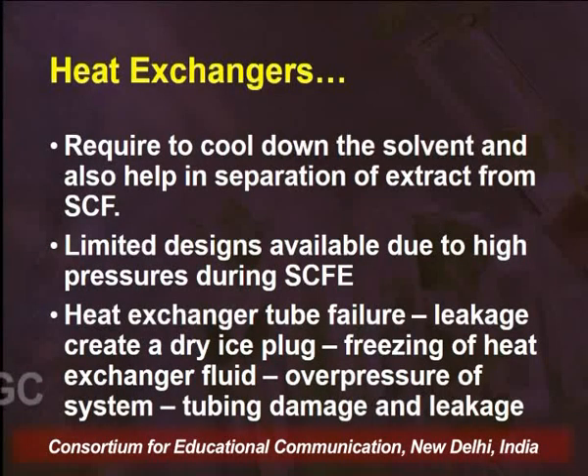And this kind of ice plug will lead to the freezing of the heat exchanger fluid. The fluid that is being circulated through the heat exchangers to maintain the temperature, whether to increase or to decrease or to maintain the prescribed temperature, if that fluid freezes, the basic purpose of the fluid, that is to exchange the temperature, to maintain the temperature, will not be achieved, and therefore it will cause damage to the heat exchanger. And once the heat exchanger stops functioning in this manner, it leads to the overpressuring of the system.